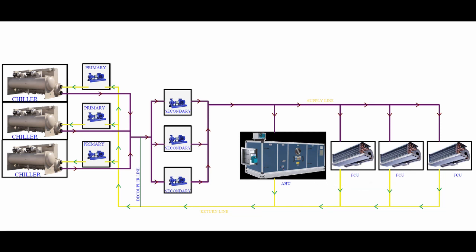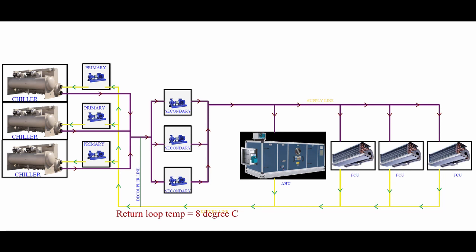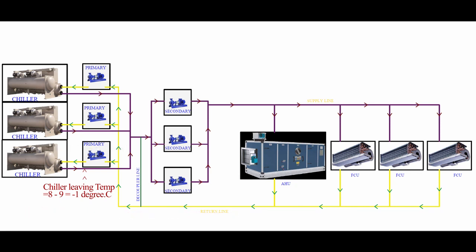So this 8°C return chilled water will be going back to the chiller. The chiller always needs a minimum flow rate — that is why we use the primary pump. The chiller delta T is 9°C, fixed as per the design calculation. Now for the chiller: the inlet temperature is 8°C and the delta T is 9°C, so the leaving temperature will become minus 1°C. Water will freeze at this temperature and it should not happen. This is called low delta T syndrome.